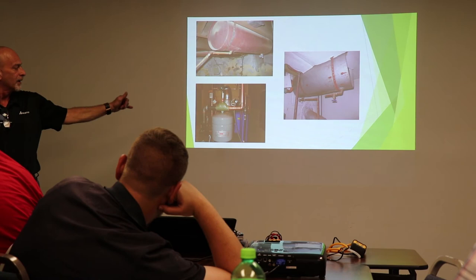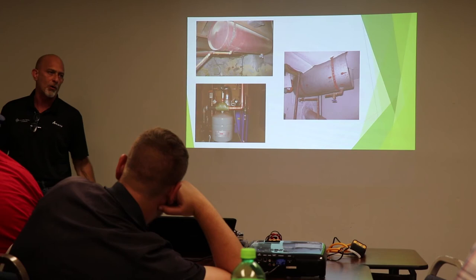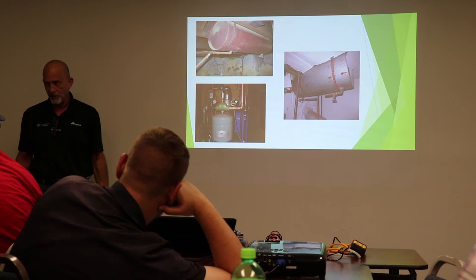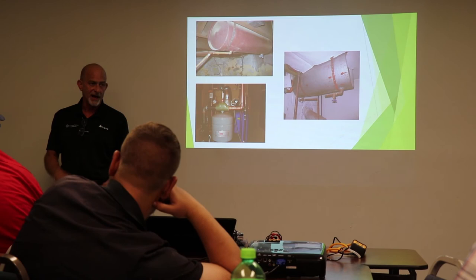Keep in mind, every time we take a boiler system down, if we drain it down, we have to bleed the air out of this system. There are a lot of systems out there that didn't have bleeder valves put in, didn't have valves to bleed it.